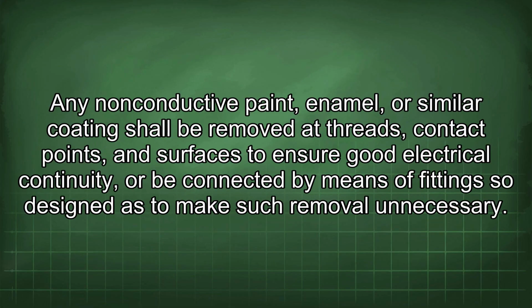Any non-conductive paint, enamel, or similar coating shall be removed at threads, contact points, and surfaces to ensure good electrical continuity, or be connected by means of fittings so designed as to make such removal unnecessary.